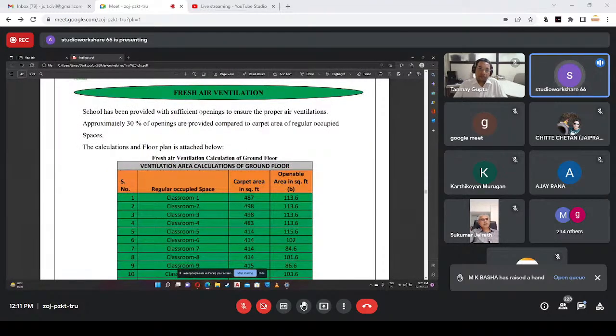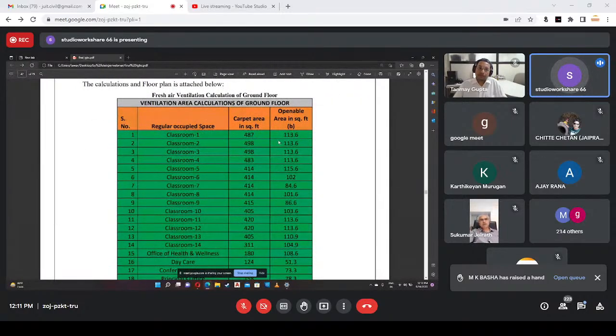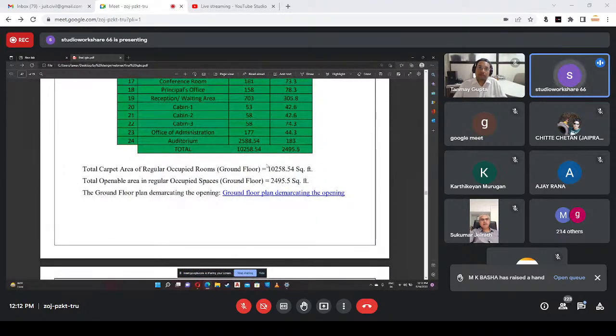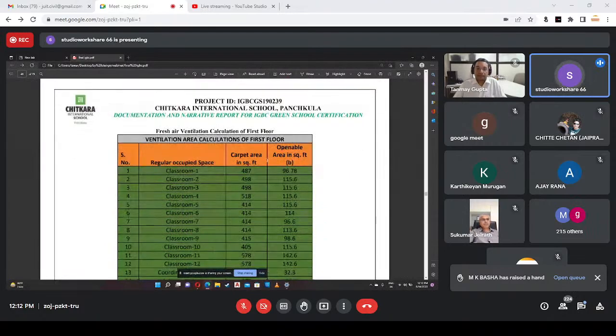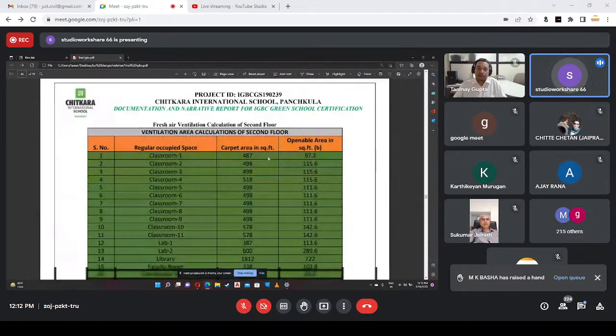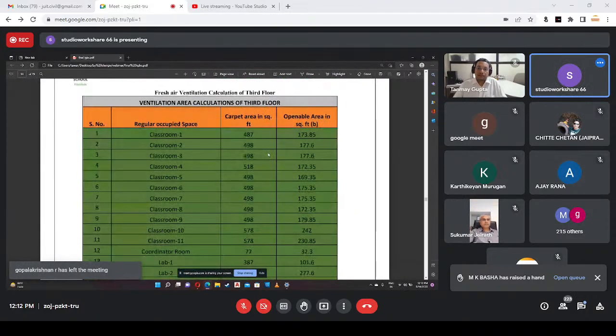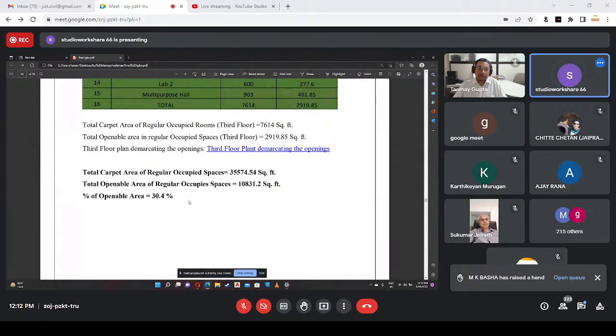For fresh air ventilation of each classroom, we are required to ensure that 30% of the openings are provided compared to the carpet area of regularly occupied spaces. So if you have 100 square feet of carpet area, you need 30% openable openings that let in air and oxygen. This openable area versus carpet area needs to be demonstrated to IGBC to show proper ventilation. We submitted these fresh air calculations for all floors and occupied spaces. We achieved 30.4% openable area for the regularly occupied spaces.